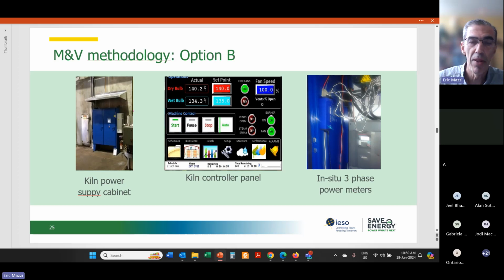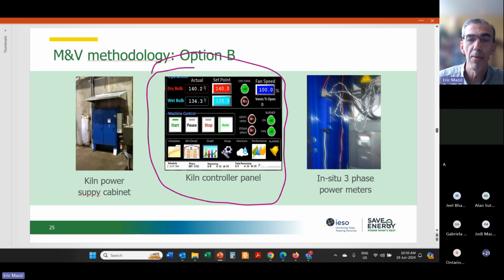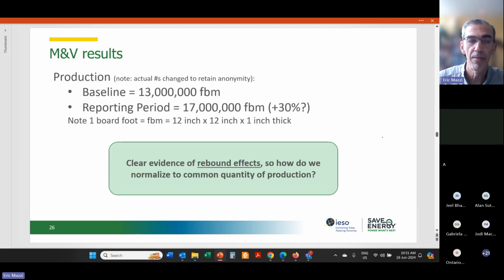So there was a power supply driving all these fans. There was like a proprietary algorithm built into the whole process. So it was not just variable speed operation. It was actually metering things like temperatures and humidity levels, used to modulate the firing rate of the burner and also the speed of the circulation fans. And we had the DENT 3-phase power meters you can kind of see here on the right.